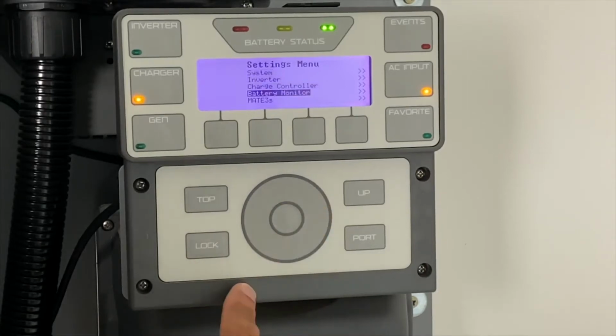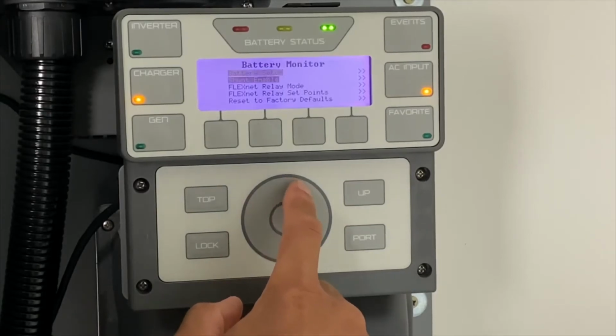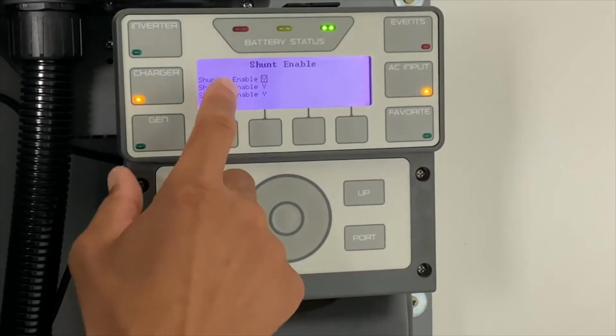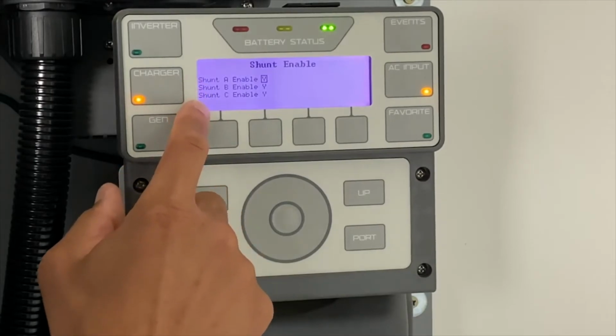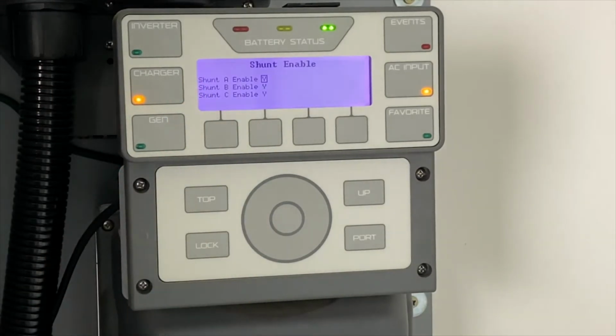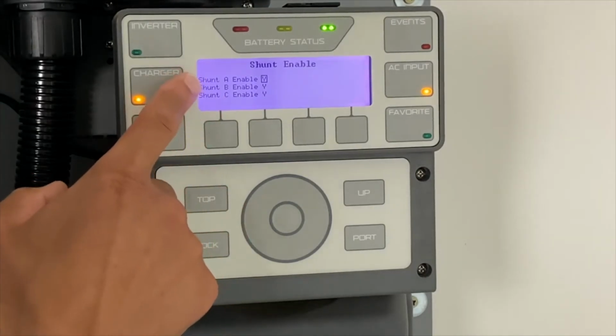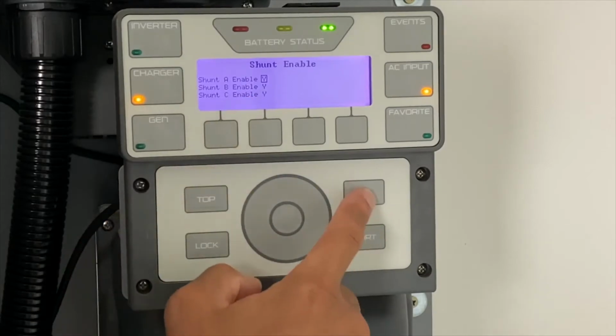First we're going to go to battery monitor, and next to shunt enable. Make sure shunt A, B, and C are all enabled. This is very important because this unit has an advanced battery monitoring system, and we want the energy flowing through the system to be tracked properly, so we know how much is going into the battery, how much is coming out, how much is going back to the grid, and so forth. A, B, and C all need to be enabled.